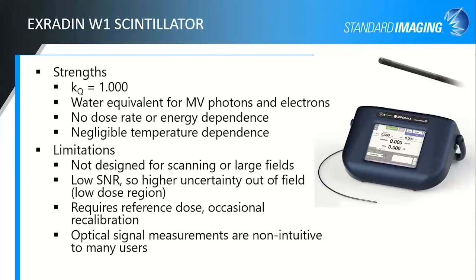The strengths of the W1 are that kQ value of 1, as shown in the TRS 483 publication. It is water equivalent for megavoltage photons and electrons. We don't see dose rate or energy dependencies with this. There is a very small temperature dependence. It's about 0.1% per degree Celsius. But as long as you're doing all of your measurements at room temperature or close to room temperature, then there is no need to make that correction.